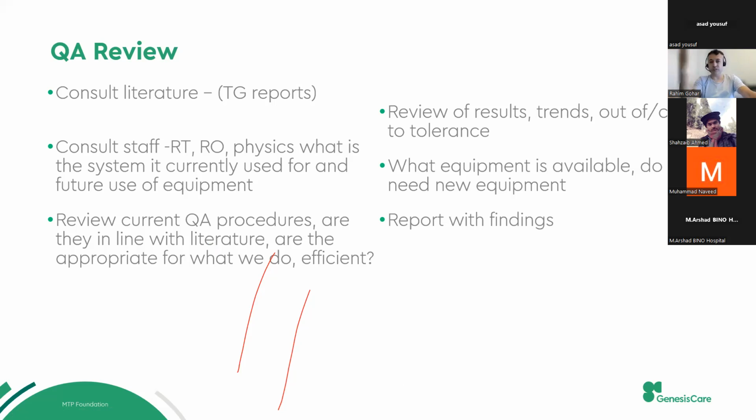If I remove them, what's the risk? If you want to add something, you will add something. And one more important thing is the trend as well, and the tolerances and the reports and the findings. What are your findings? What are your trends? So these are the things you need to look at when you are talking about the QA program in any LINAC or a CT.